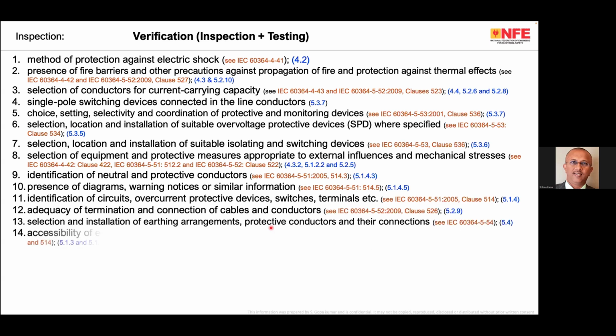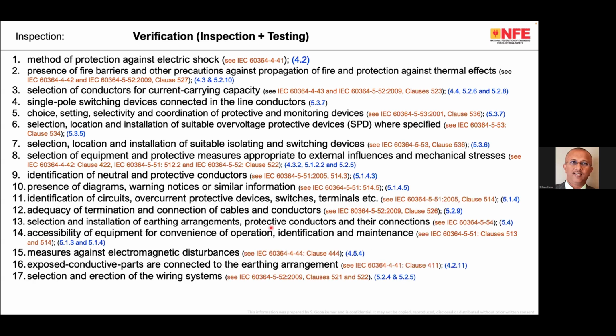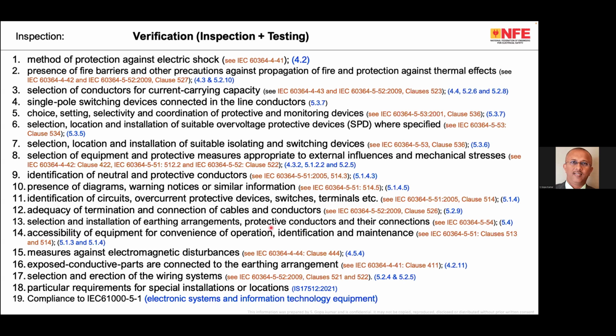There are different verification points. Verification starts with inspection. There are about 19 points to inspect, starting with protection against electric shock, which is not the important one with respect to fire, but the second one, presence of fire barriers, other precautions against propagation of fire, and the protection against thermal effect. It is a point of inspection, which you can see in blue, 4.3 and 5.2.10 of IS 732.